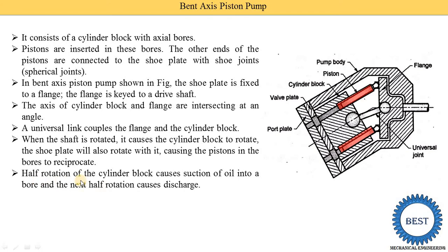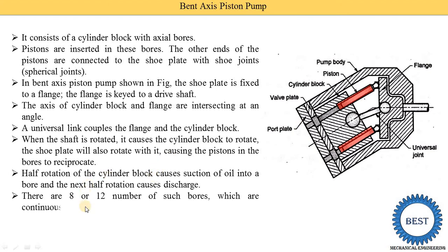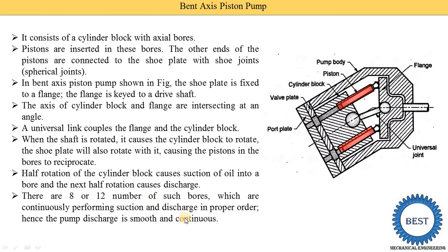Half a rotation of the cylinder block causes suction of fluid into the bore, and the next half rotation causes the discharge. So from one side suction takes place and from the other side discharge takes place. There are 8 or 12 such bores which continuously perform suction and discharge in a proper order — for example, at 0 degrees, suction is going on in 2 bores, and after 45 or 60 degrees, delivery is going on in 2 bores. This proper order is decided in advance.